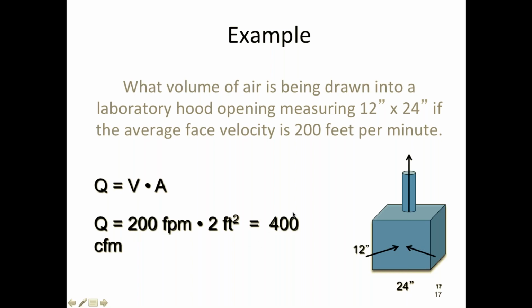If this is 800 and this still is 2 square feet, then this would be 400 feet per minute face velocity. It's pulling air in quicker. If you have a hood that you're working with that has a relatively non-hazardous material, you might want to keep the face velocity of air getting pulled in at 50 to 100 feet per minute. If it's a more dangerous material, you might want to keep it at 200 feet per minute to ensure that whatever's in that hood stays in that hood.